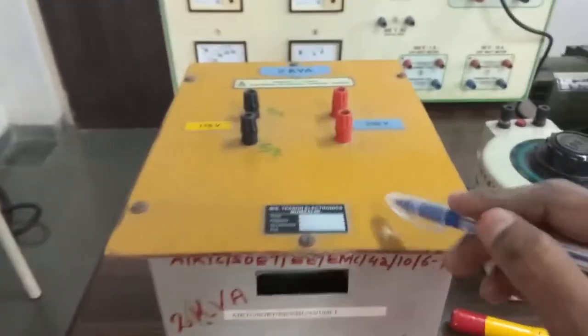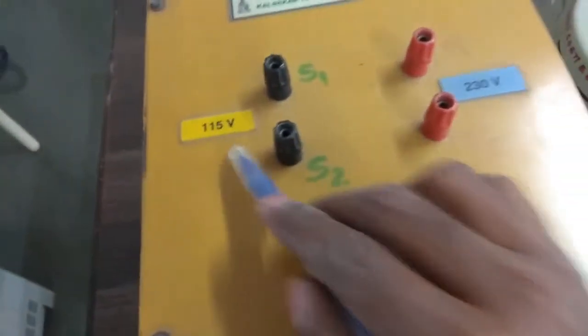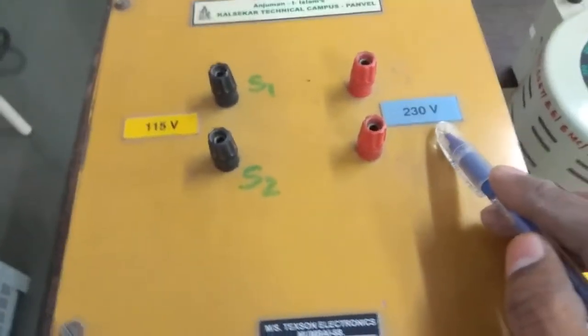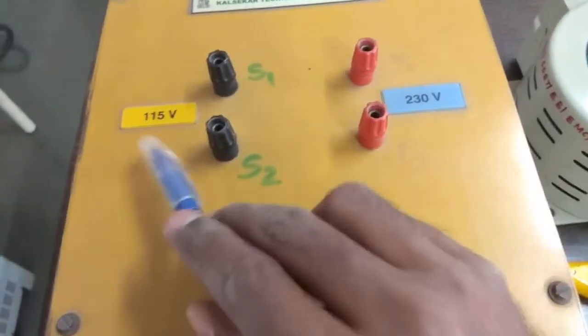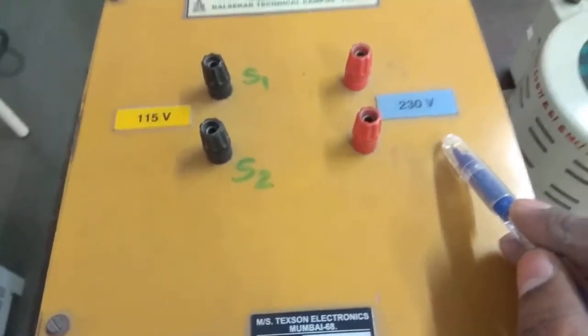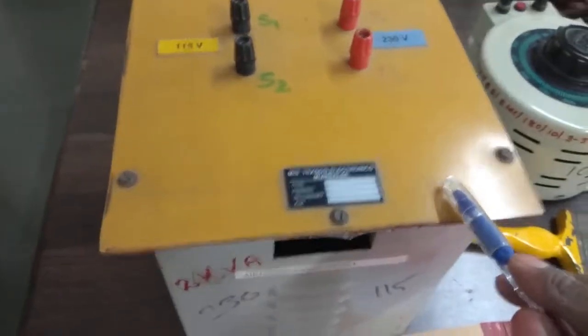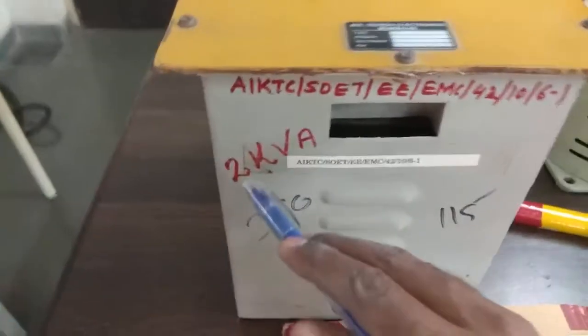This is our transformer on which we will perform the practical. This is the LV side of the transformer and this is the HV side of the transformer. LV is 115 and HV side is 230 volt. This transformer on which we are performing the practical is of 2 kVA.